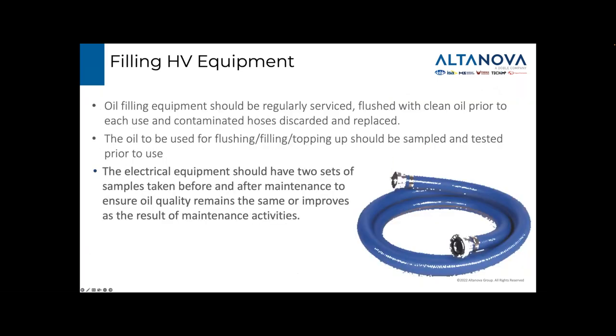For filling HV equipment, take time to check pumps and hoses used for oil management activities before use. If the contamination is so high that flushing with clean oil prior to use will not clean them, then they should be replaced. Any contamination of oil filling equipment will be transferred to the apparatus. So remember to take 2 sets of samples from the asset before maintenance, and also test the oil for topping up prior to use to ensure it's within specification.